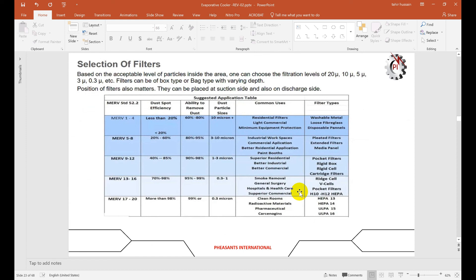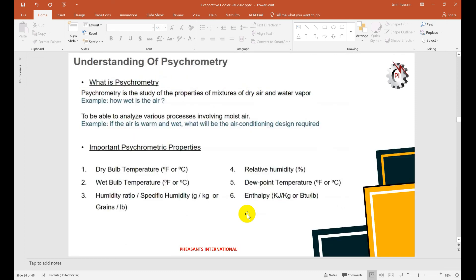For filters: residential purposes use G1 to G4 filters controlling 10 microns; industrial and commercial applications use filters for 3 to 10 microns; better industrial and commercial environments use 1 to 3 microns. For surgery and hospitals, filters down to 0.3 to 1 micron are used, and for clean rooms and pharmaceutical areas, filters at 0.3 microns are required. Before understanding indirect or direct evaporator cooling, it is important to understand the basic concepts of psychrometrics, which will be covered in the next slides.